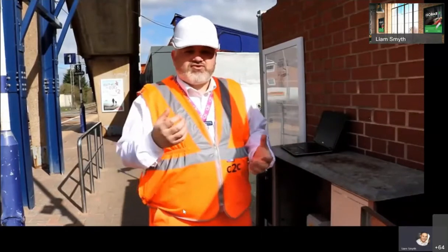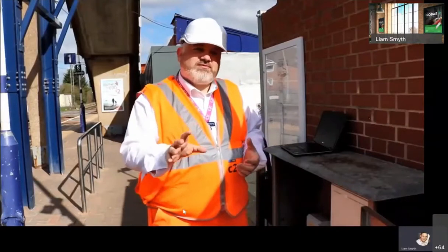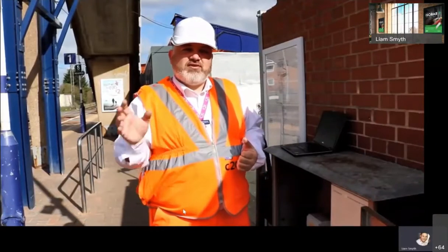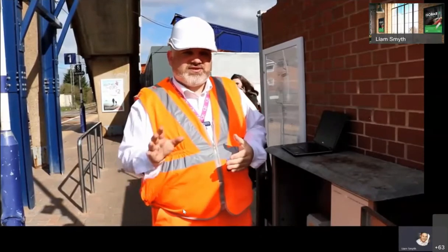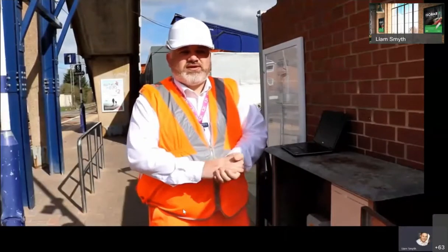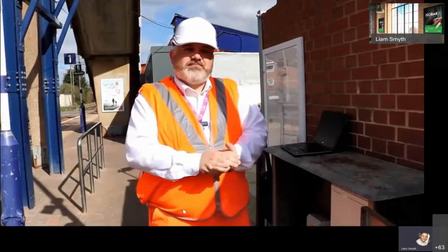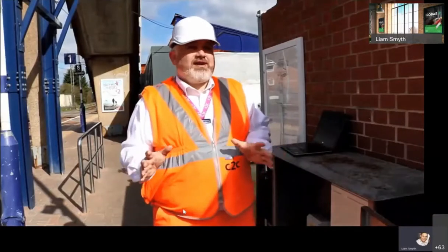And also, if something trips out, you know straight away. But more importantly, one of the things that we have found is when there has been a near overload, we can actually send a guy out to check why the breaker is nearly tripped, which is an amazing feature. And then 99% of the time he finds that there may be a loose connection, or somebody's installed something not as per the design. So it's fascinating technology, because it's predictive, it's active, but inherently, if you set the alarms up well, you immediately go into a predictive, this can fail, this will happen, go out and look before the event happens. I didn't expect that, and that has absolutely blown me away.